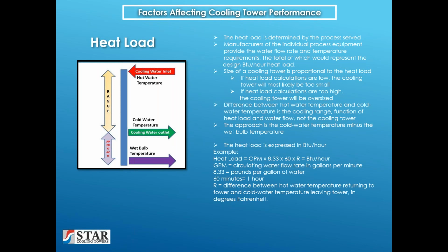The heat load is expressed in BTUs per hour. So if we take the GPM times 8.33, which is the weight of 1 gallon of water, times 60 minutes, times the cooling range, it gives us our BTUs per hour. So if the flow rate changed, you would see that the cooling range would change, either increase or decrease, or if the BTU load itself changed, we would be seeing a different cooling range.